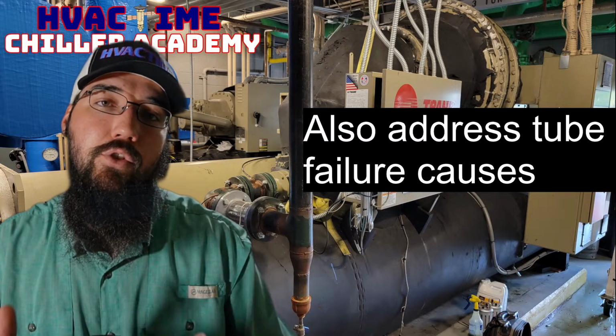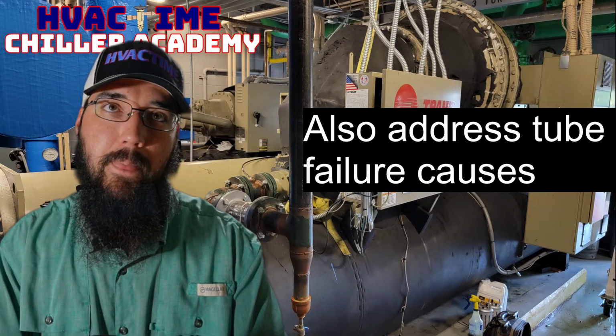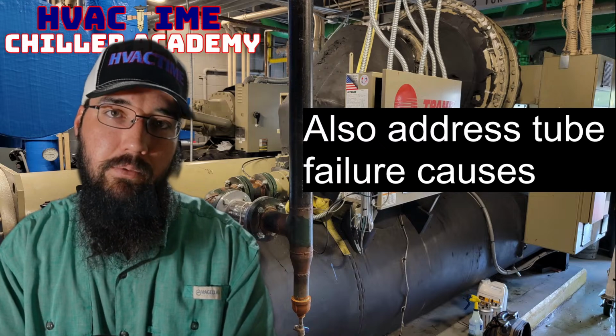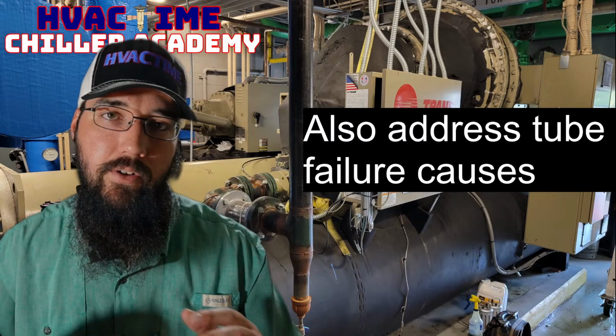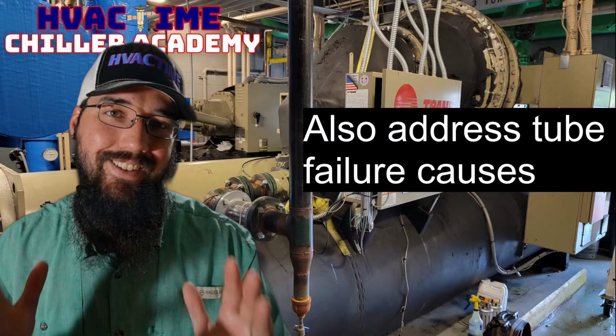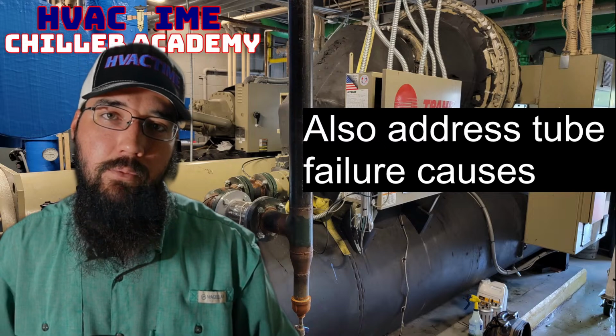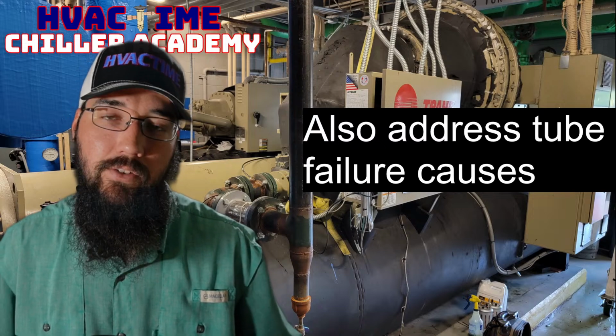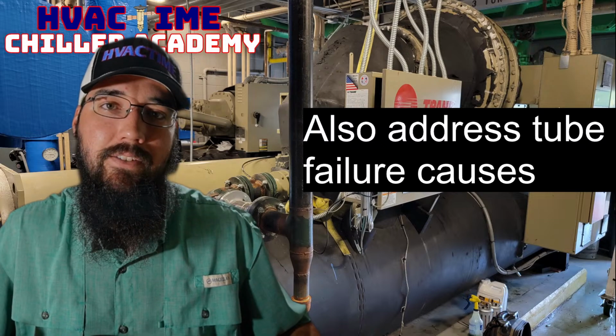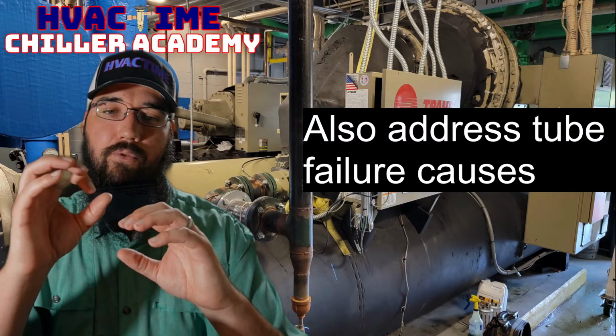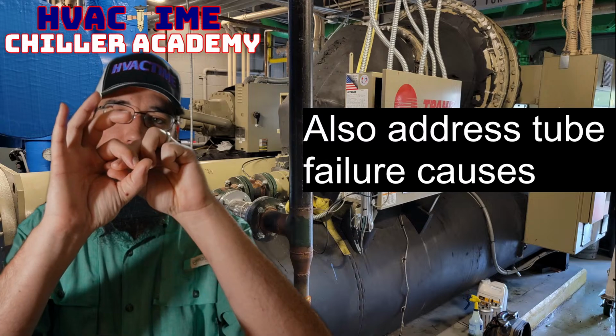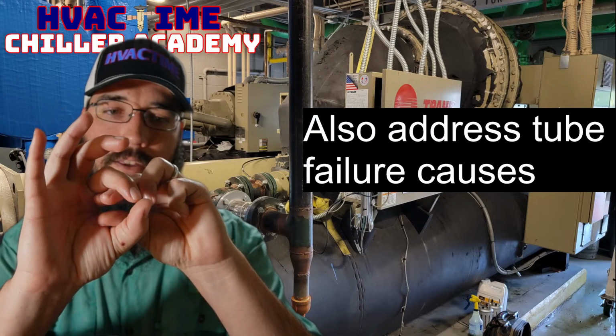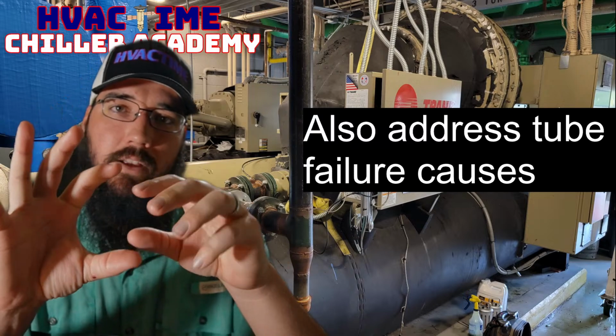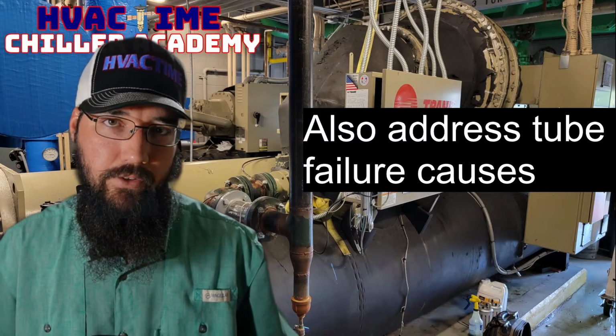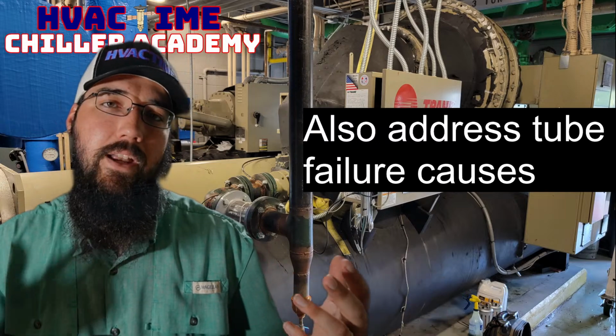So the tubes freezing. Basically, the ones that are most susceptible to this would be a flooded or a falling film design where the water is inside the tubes. And essentially when water freezes, it expands. If you've got your tube and a little bit of water gets frozen in there, it expands and just straight out ruptures that tube and busts it. So that is one way.